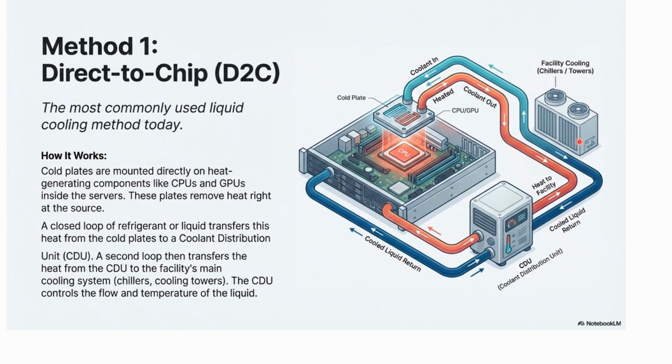So clean liquid cools the chips, gets hot, dumps its heat to the facility water inside the CDU, and then goes right back to the chips. It's a perfect compartmentalized system. It ensures a problem with the building's plumbing doesn't take down your multi-million-dollar AI cluster.